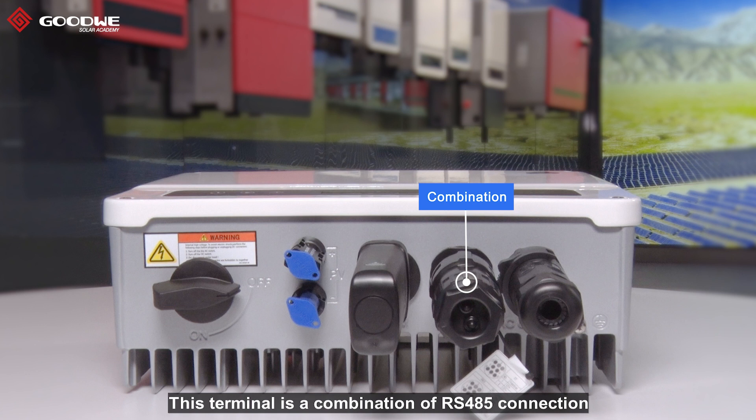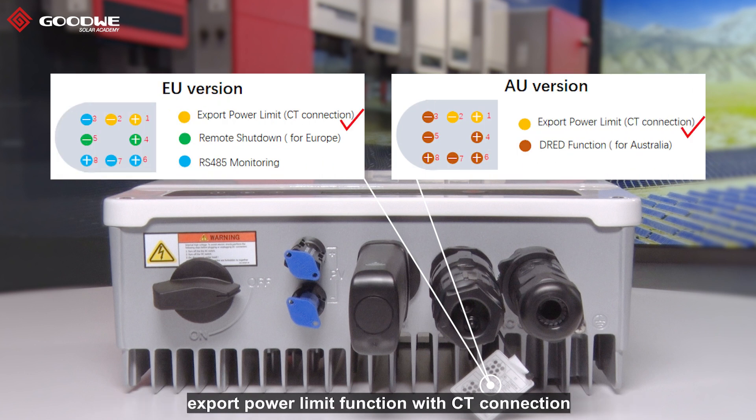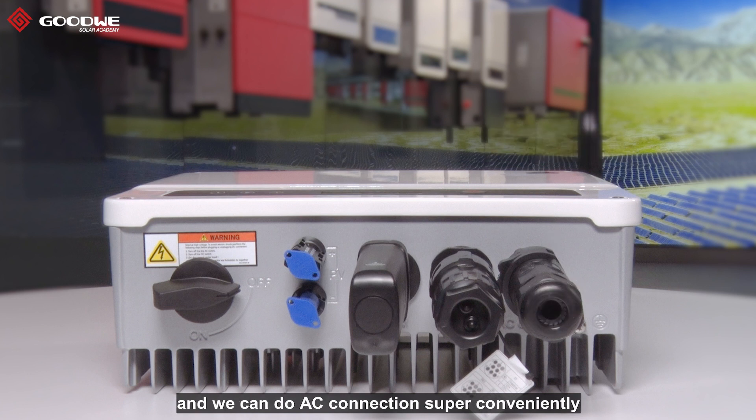This terminal is a combination of RS-485 connections for multiple purposes, such as monitoring multiple inverters in daisy chain configuration, export power limit function with CT connection, and remote shutdown function in Europe, or DRED function in Australia. For the AC terminal, we provide a new type of AC connector so we can do AC connection super conveniently.